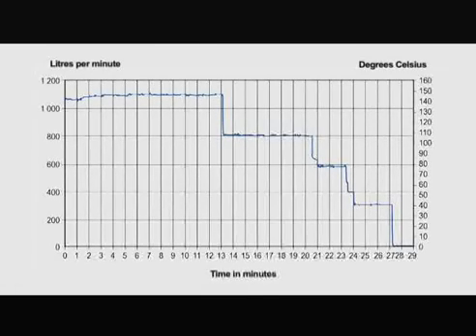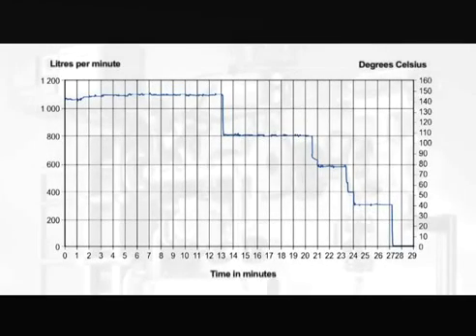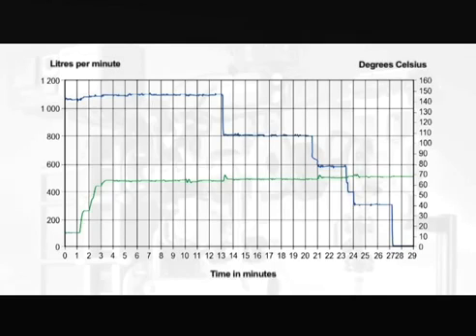This example shows a typical domestic hot water service illustrating water heating with a high secondary temperature fall and large sudden load changes. The steady secondary temperature is maintained within plus or minus 5 degrees Celsius on an instantaneous duty, without a storage tank or buffer vessel in the secondary circuit.